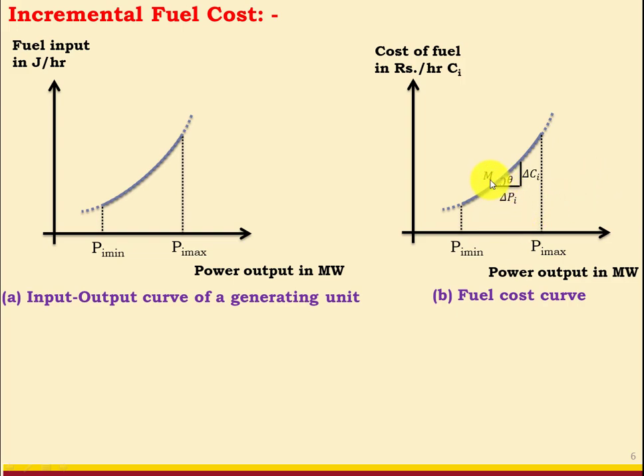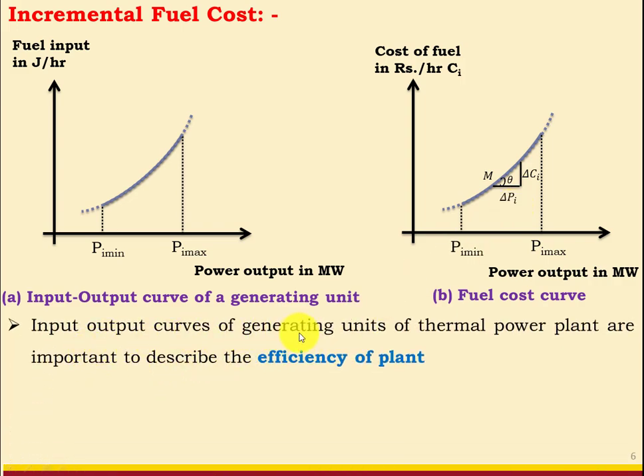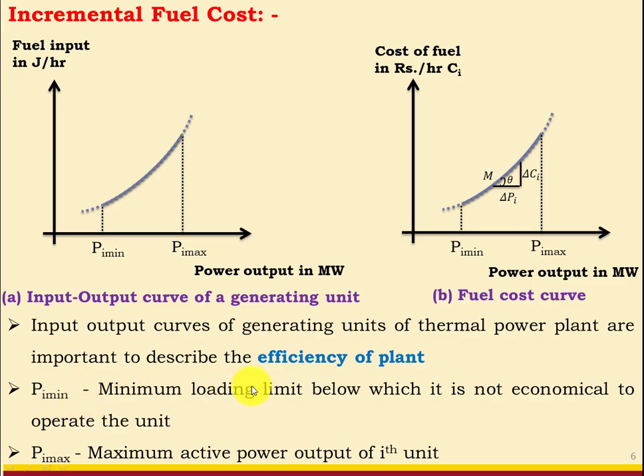We want to take the slope of this cost curve. Even though the curve is non-linear, for a small part we can assume it is linear. The slope is calculated as tan θ = ΔCi / ΔPi, i.e., increase in cost of fuel divided by increase in power. The slope is change in y divided by change in x. Input-output curves of generating units are important to describe the efficiency of the plant. Pi_min is the minimum loading limit below which it is not economical to operate the unit; Pi_max is the maximum active power output of the ith unit.